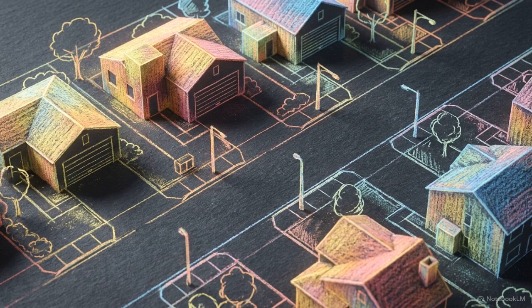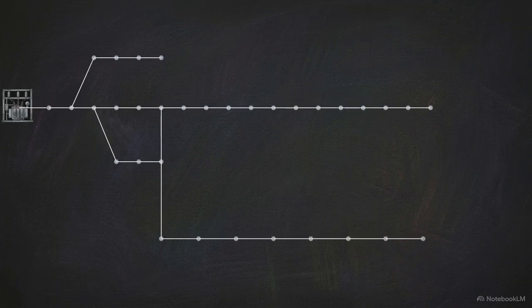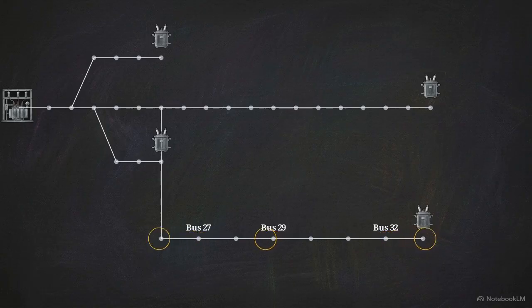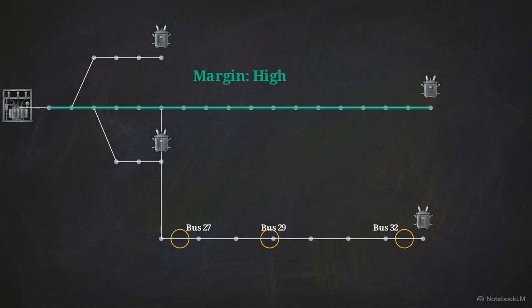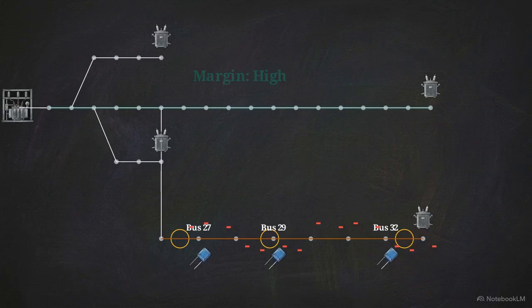The 75% EV light scenario simulates daytime operating hours when home charging penetration is at its lowest. The algorithm evaluates the network and clusters all 3 capacitor banks strictly at buses 27, 29, and 32, the extreme tail end of the feeder. The engineering logic here is straightforward. Under light loads, the upstream trunk has plenty of voltage margin. The reactive power shortages are entirely localized at the farthest nodes.